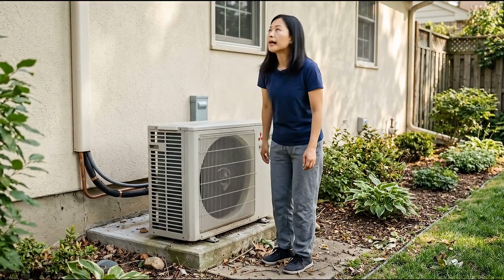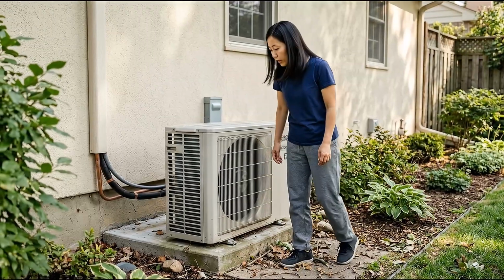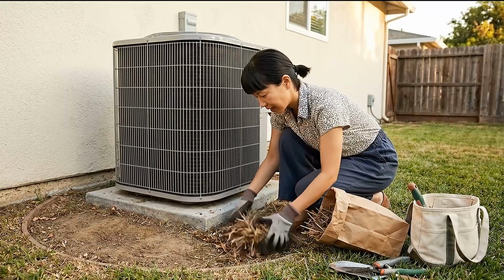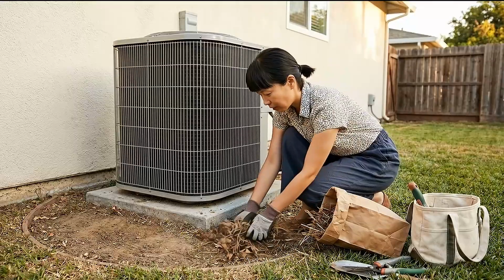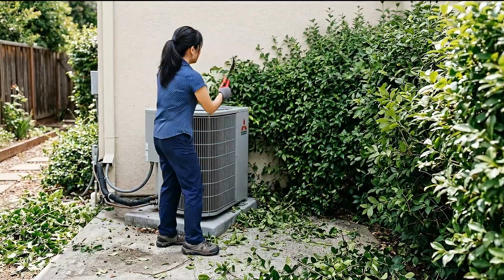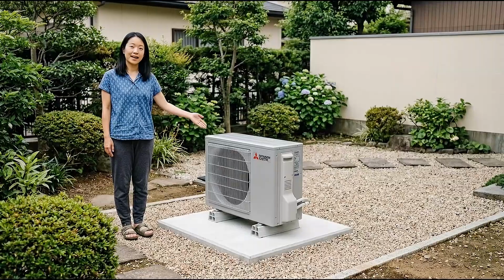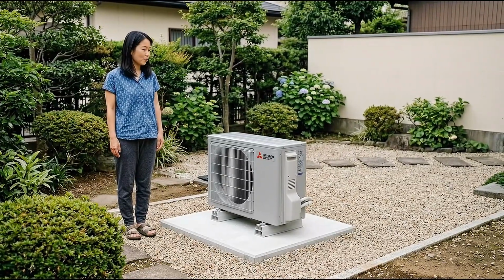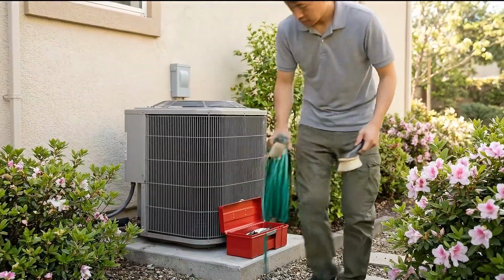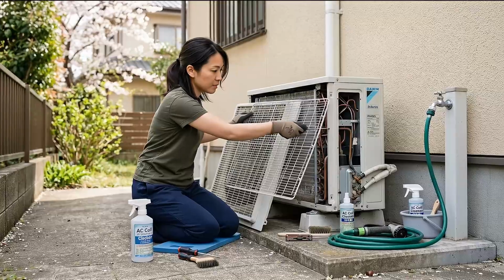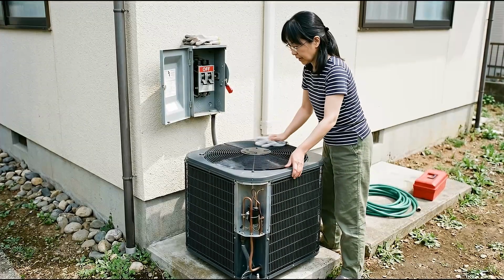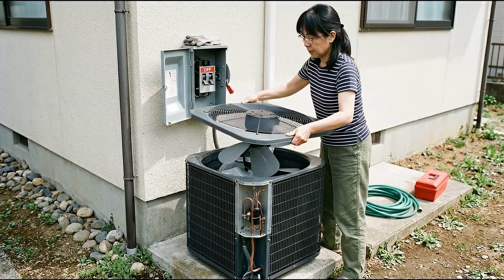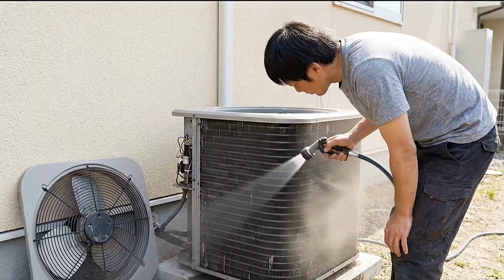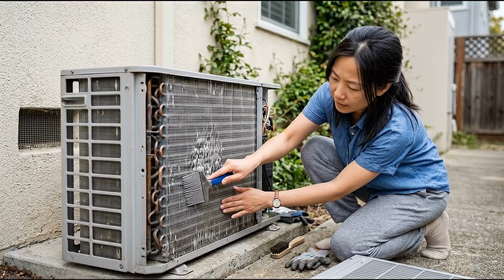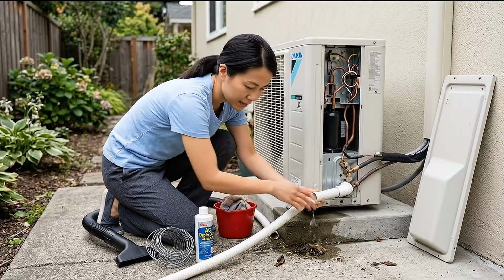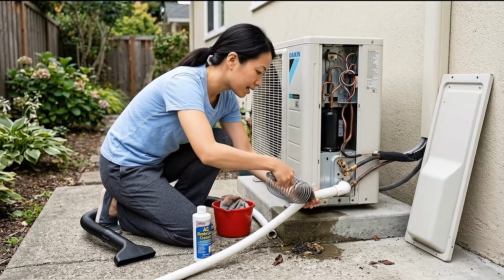Every month during cooling season, check the area around your outdoor condenser unit. Clear any leaves, grass clippings, or debris within 2 feet of the housing. Trim back any vegetation that has grown close to the unit. The condenser needs unobstructed airflow on all sides to release heat properly. Once a year, in spring, before you start running the AC for the season, do the full condenser coil cleaning. Kill the power at the disconnect. Remove the top grill or fan assembly if your model allows it, and hose the coil fins from the inside out. Straighten any bent fins with a fin comb. Inspect the condensate drain line while you are there and clear it if it looks sluggish.